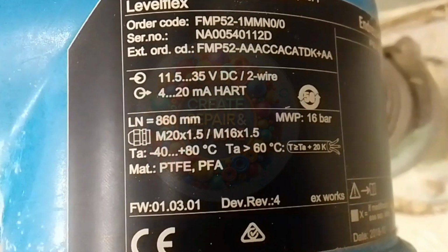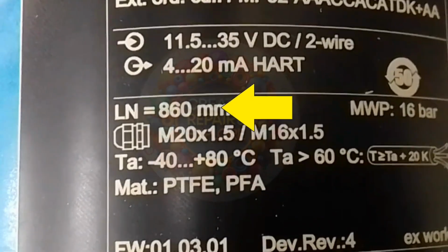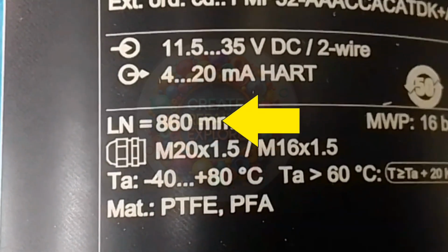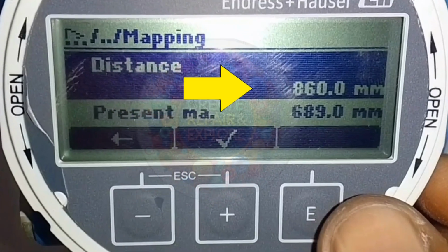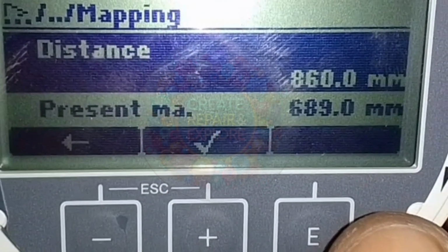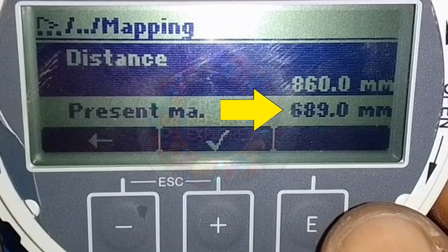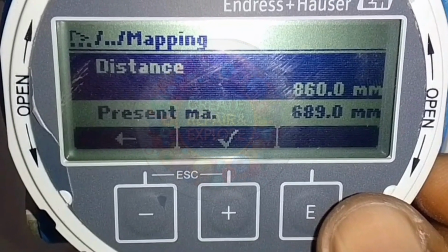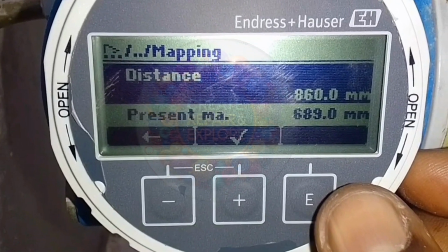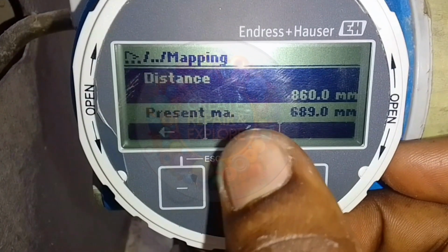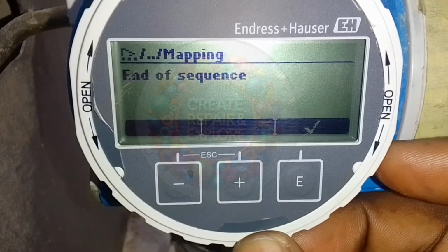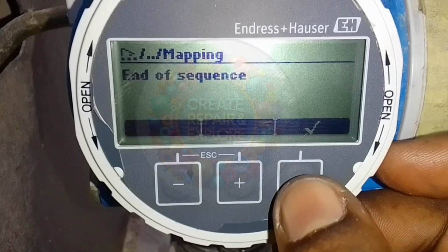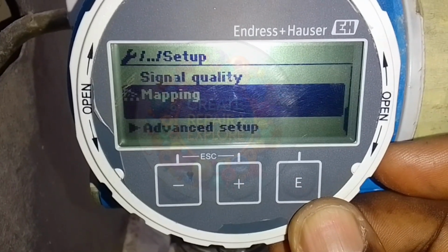You would see that the 860 millimeters coincides with the value you have on the screen. The value below the 860 millimeters is the maximum value of the probe, which is automatically calculated by the probe. So if the values you are getting are correct, press the plus button that is underneath the check mark on the screen. Now press the enter key to end the mapping sequence.